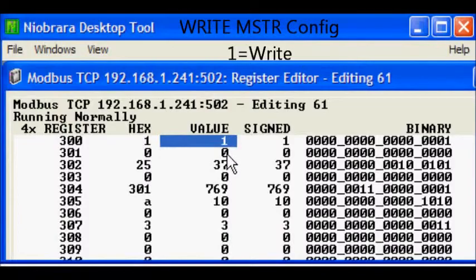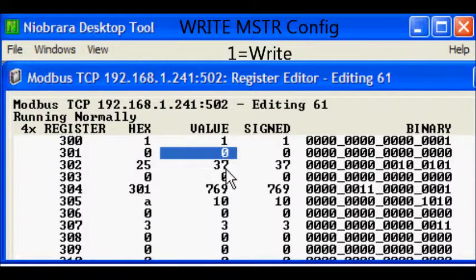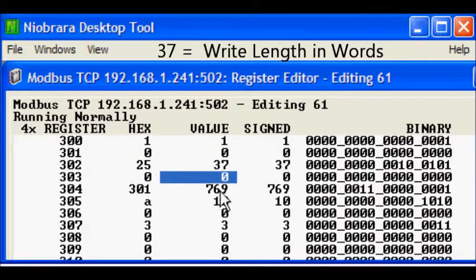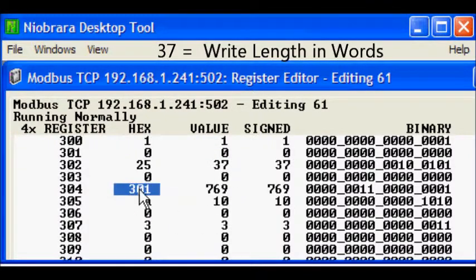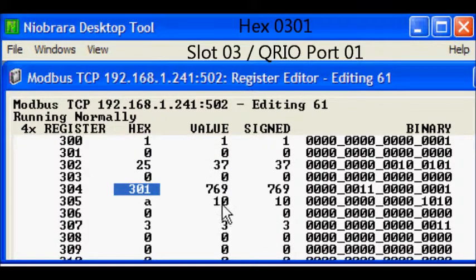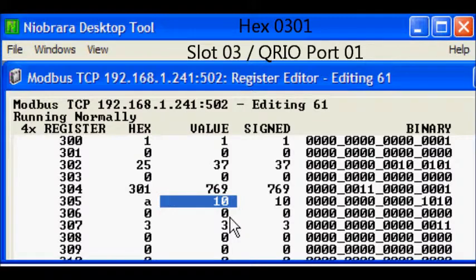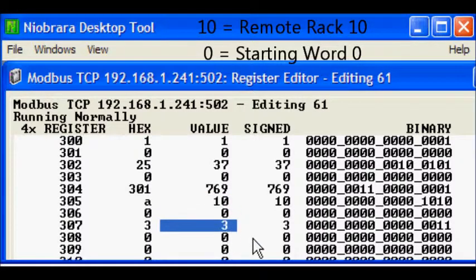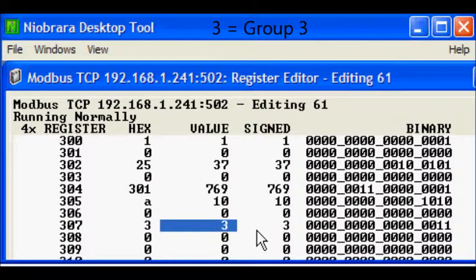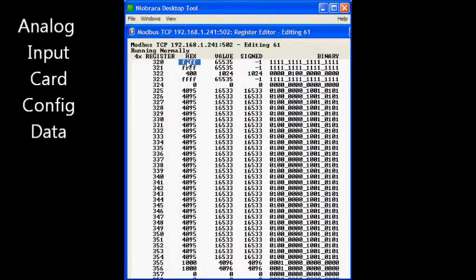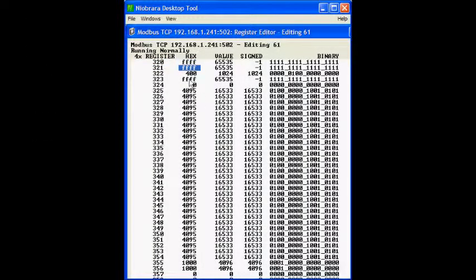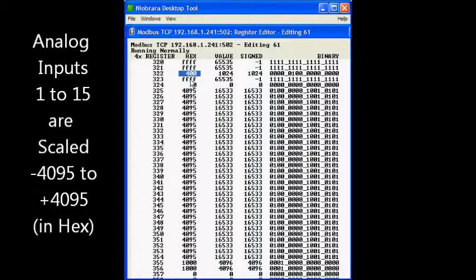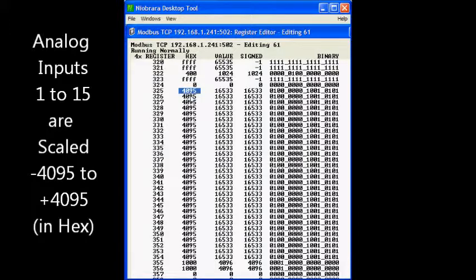The control block for this MSTR starts at register 300. The value 1 selects a write. The analog input card requires 37 words of data for its configuration. The configuration data starts at register 320 and includes bitmaps for enabling channels and setting their ranges and scales. Note that this analog card requires the input scales to be entered in BCD hex and not decimal.